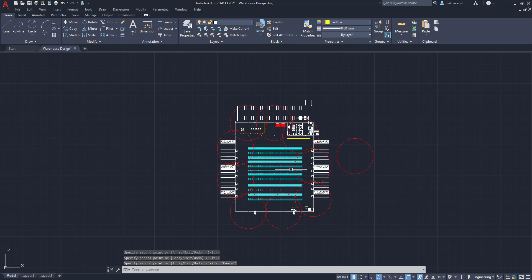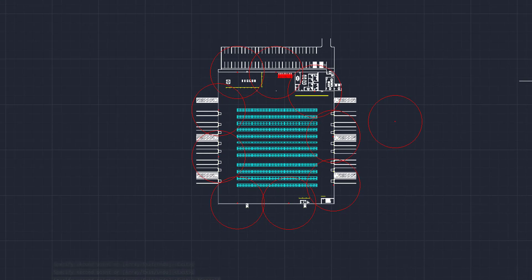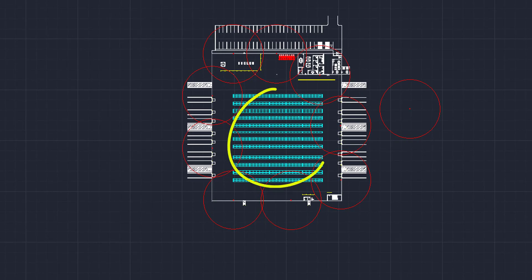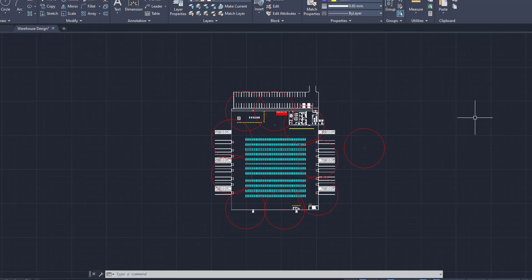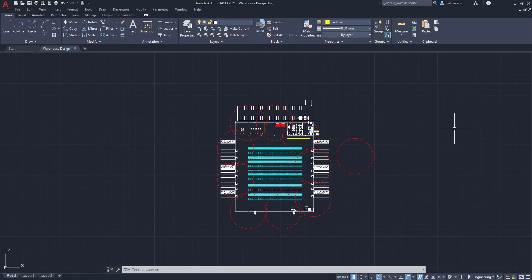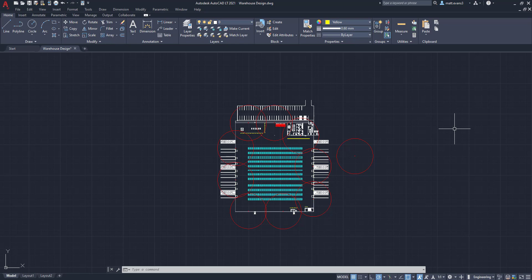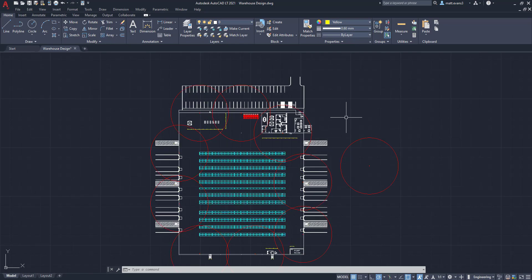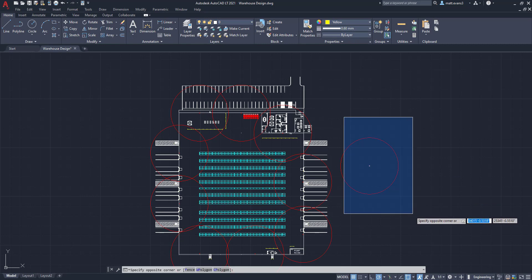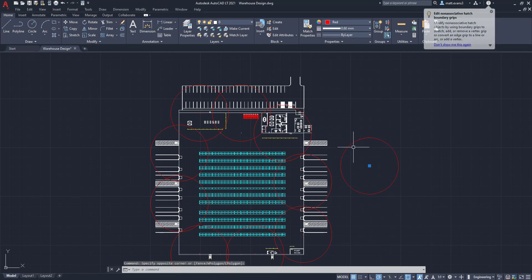You'll notice that there is a massive area in the middle, this gap area, that doesn't have any fire extinguishers. Based on where you're at, you don't necessarily need fire extinguishers in the rack. Because this area is not available for personal or pedestrian use, there is no need to have a fire extinguisher in the middle. So what we're going to do instead, it doesn't need to be covered in the rack. The rack is an exemption.